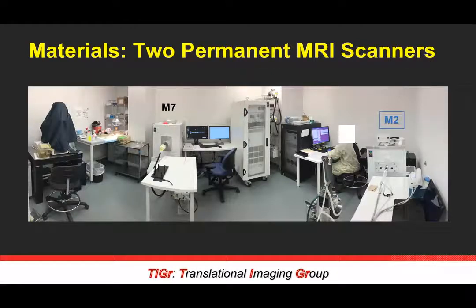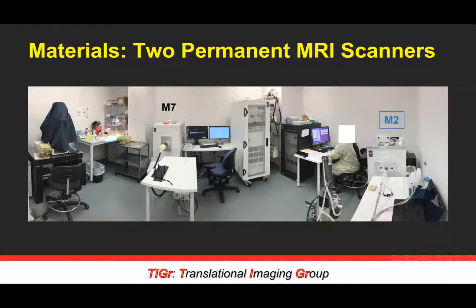The GRE sequence uses 0.5 millimeter cubed isotropic resolution and is a 15-minute scan as we cycle through five different flip angles for calculating T1 values using a variable flip angle method. In our lab we have two of these 1 Tesla permanent magnet scanners and use them pretty frequently, imaging anywhere from 10 to 30 animals a day for a variety of different research applications.